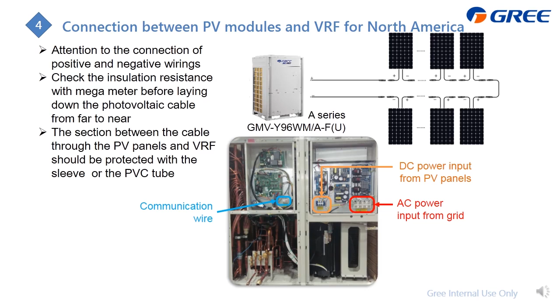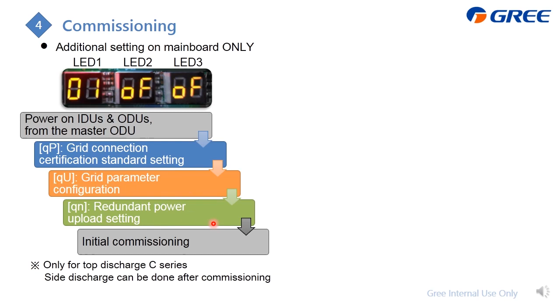After that, you need to do the commissioning. This is especially for the top discharge and especially for the C series. For that, just follow these steps. These are additional steps compared with the regular VRF, including QP, which is for the grid connection certification, then QU, which is the power supply setting, and QN, which is whether you need to upload or not upload to the grid power supply, which standard is this one.